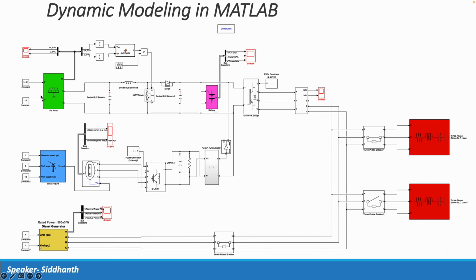As the PV array's voltage may not be stable, since it's a renewable source depending on solar irradiation, a DC to DC buck converter is required to maintain stable voltage for the DC bus, which we have selected at 720 volts. Using this converter, the voltage will be maintained at 720 volts, which will be supplied to the battery connected at 720 volts.